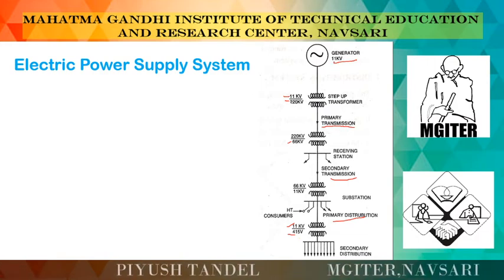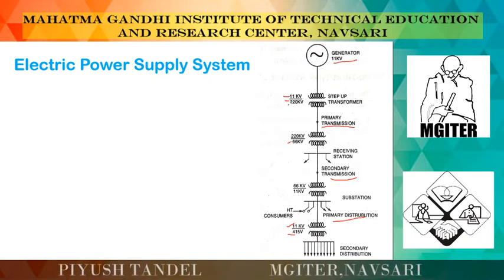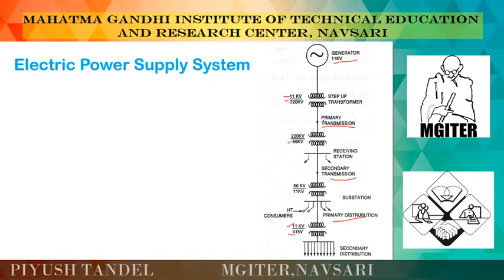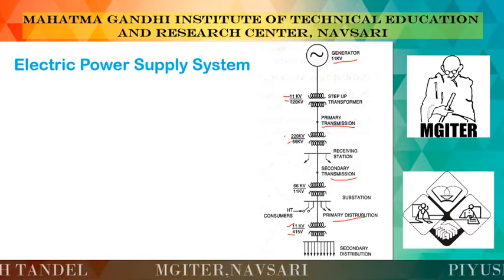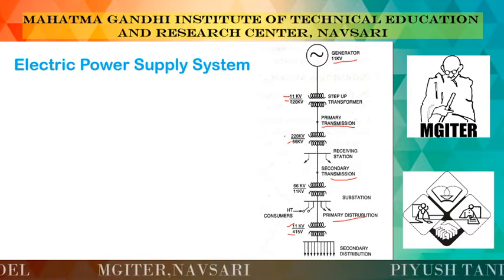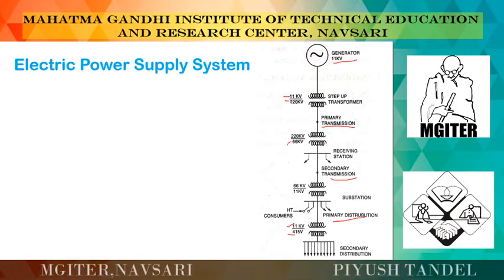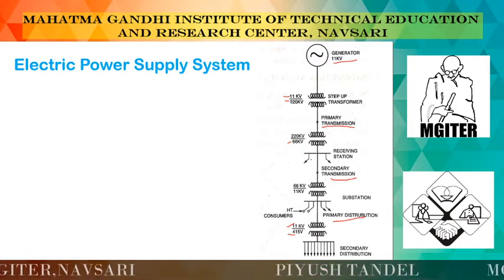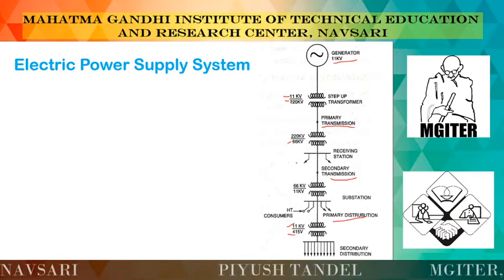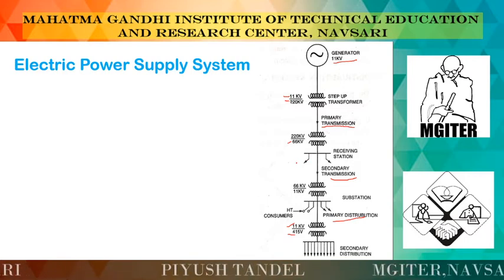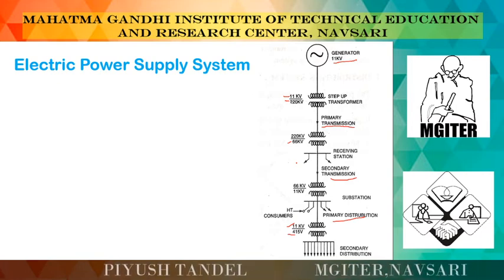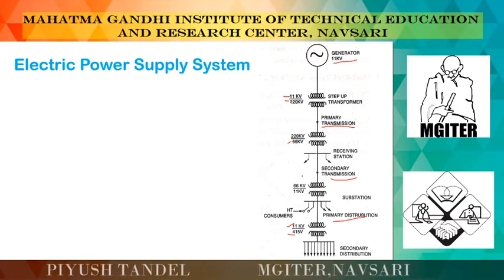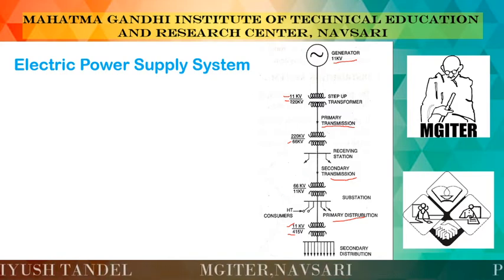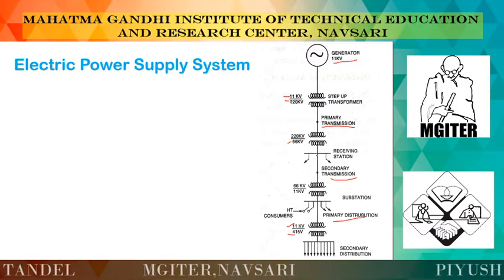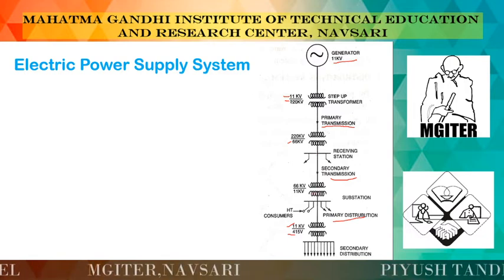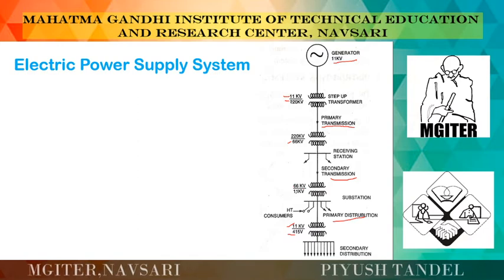First of all, the energy is generated at 11 kV, then we step it up and transmit it, and that is called the primary transmission line. At the end of the primary transmission line we convert it to 66 or 33 kV. This is at the receiving end side, so different substations require different power and different voltage levels. For that we can convert it from 66 or 33 kV to other desirable levels. Then this is called secondary transmission, where the 33 kV or 66 kV is transmitted to other substations, where it is converted from 66 to 11 kV.